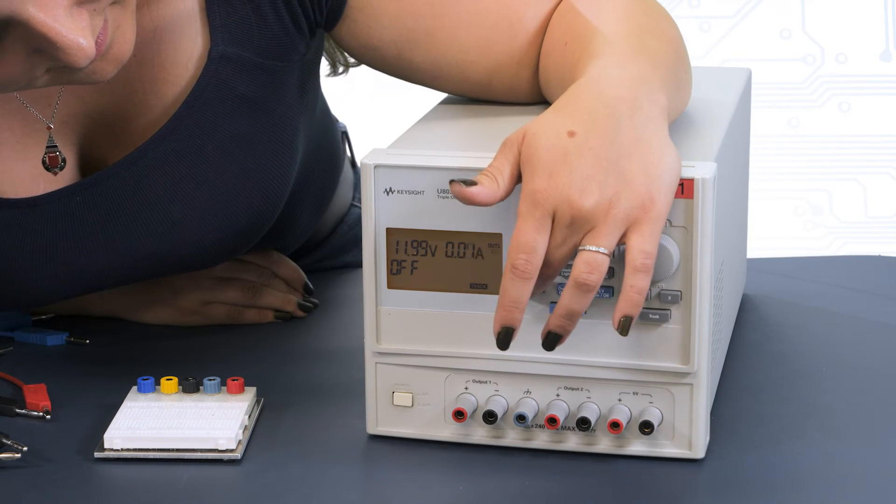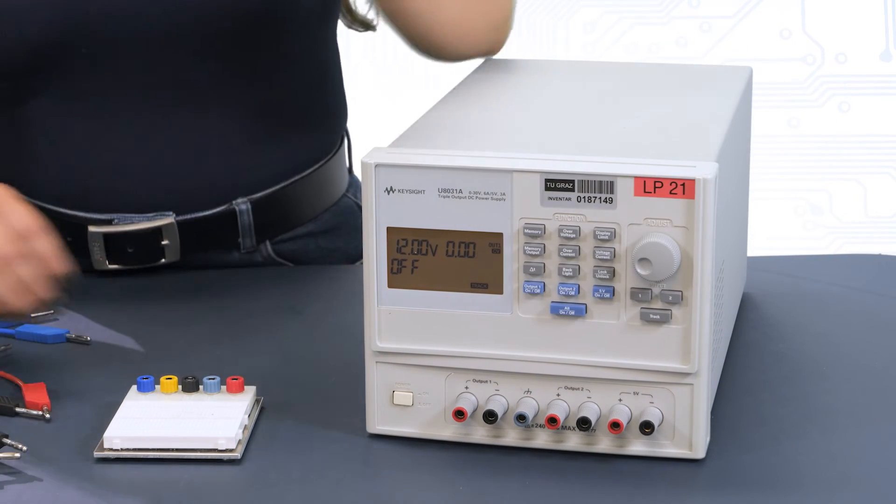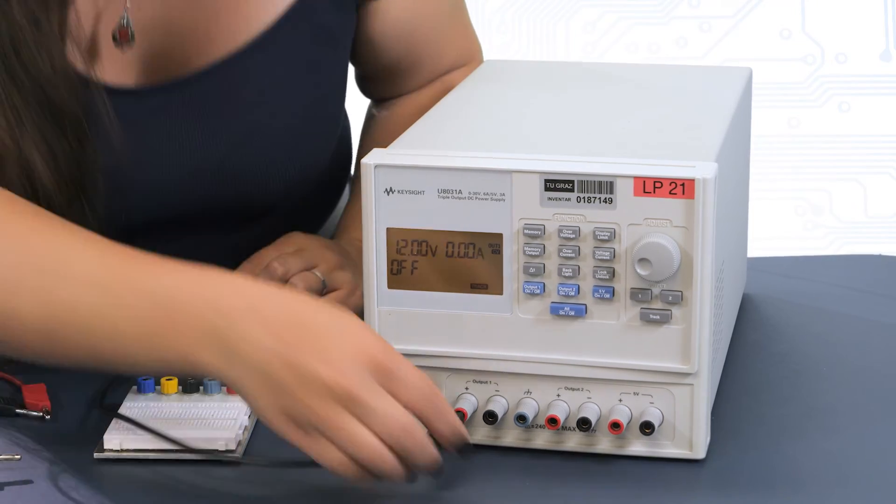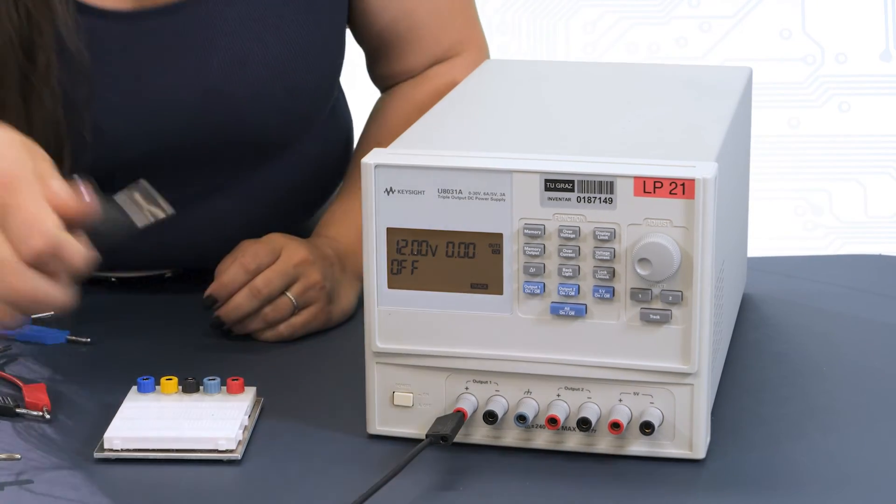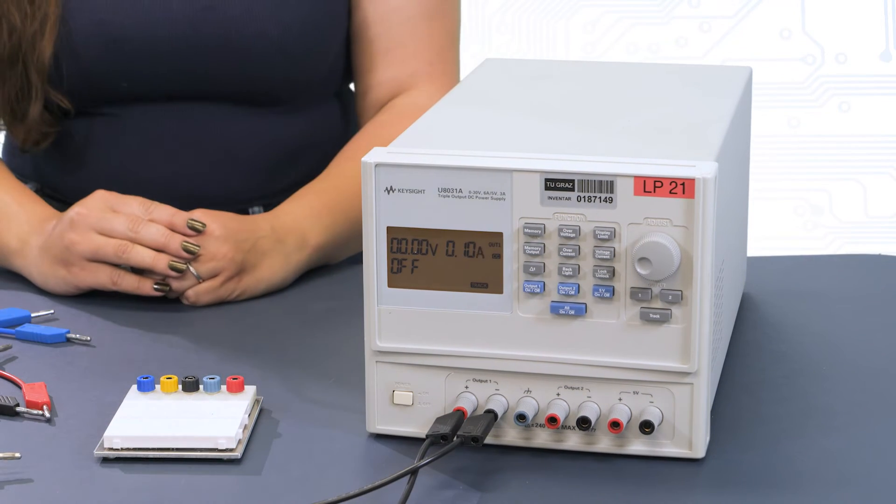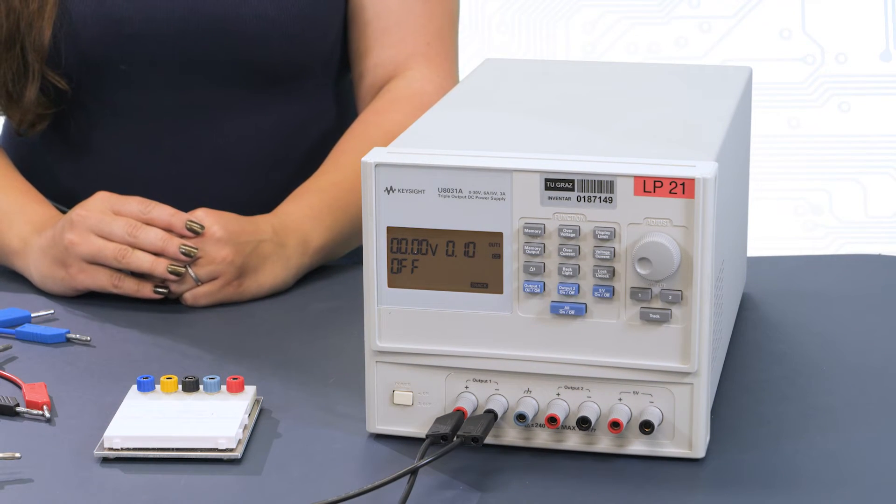Pressing the display limit button again activates the limitation. If the set current limit is reached, the voltage of the affected output is adjusted so that the current remains under the set limit in any case. The same holds true for the set voltage limit, but in this case the current is adjusted to stay below the set limit.